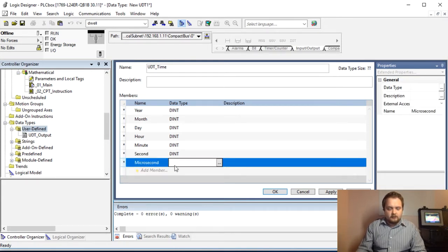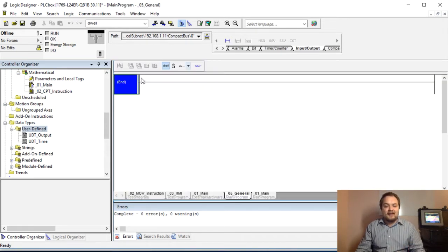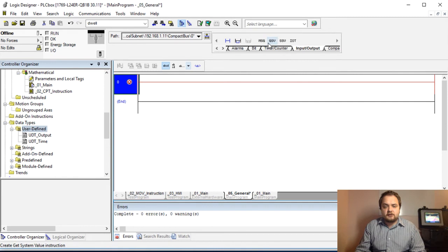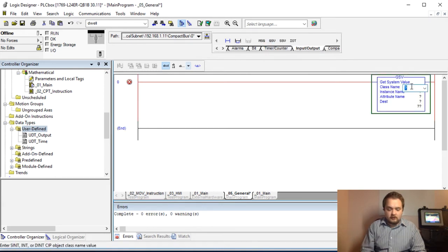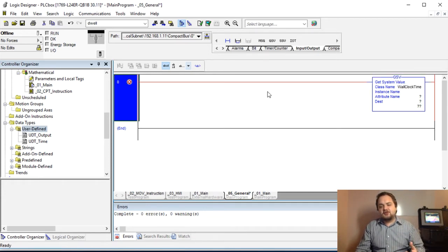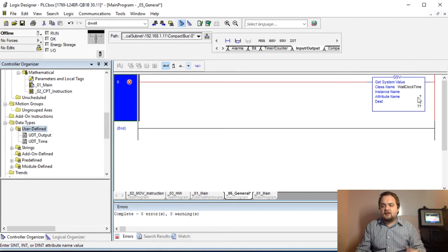That looks good, we're going to apply that — that's our time structure. To populate the structure we need to create a routine that will get the system value through a GSV instruction. GSV — Get System Value — and here we're going to specify Wall Clock Time. Wall Clock Time is essentially a register residing on the PLC that allows us to siphon that information into the tag we've created.